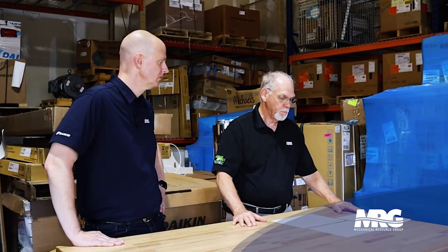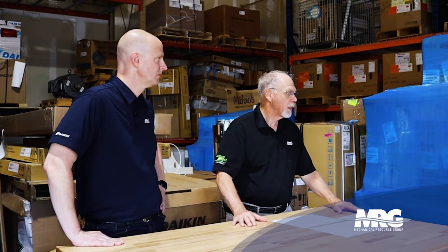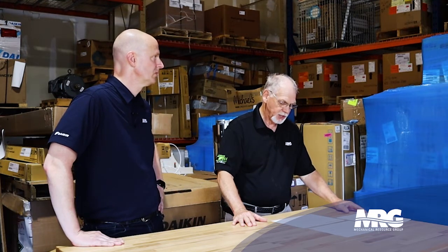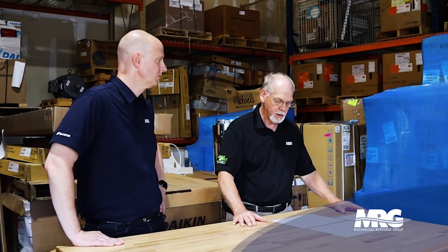The class 2 or the category 2 boilers are classified as a negative pressure condensing boiler, whereas the number 1 is the negative pressure non-condensing. So it's a natural draft, and as you're heating up your flue gases, they're going to escape on out through the roof. The condensing happens when you use a low temperature and get down below your 160, 140 degrees entering water temperature. Entering, not leaving. Entering water temperature less than 140 will cause it to start to condense.